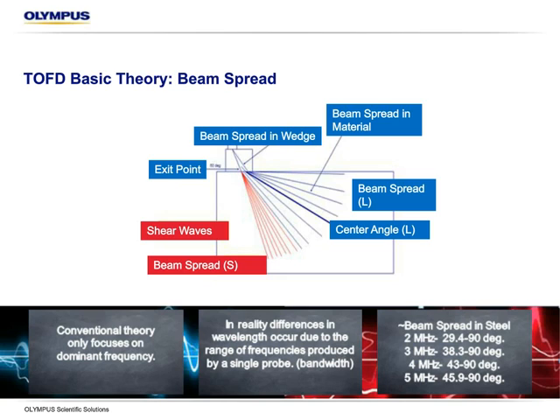For a variety of reasons we'll see, in the wedge we have a longitudinal wave. In the material we enter longitudinal waves with the center being at whatever angle the wedge is cut at. But in reality we have a whole big spread of longitudinal waves, as we can see in blue, and we also usually have shear waves occurring, which we can see in the red at about half that angle across the spread. So it's important that we understand this.